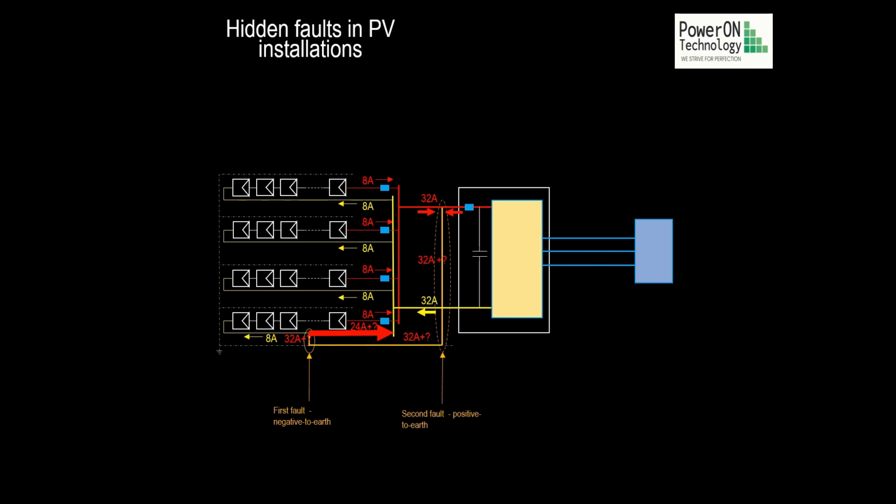These faults are potential fire hazards. The reason for being a fire hazard is because these faults overload the cables way beyond what they were designed for. Unlike AC networks, where the circuit breaker or fuse protects the next section of cable, it will be shown that this does not happen in PV wiring.